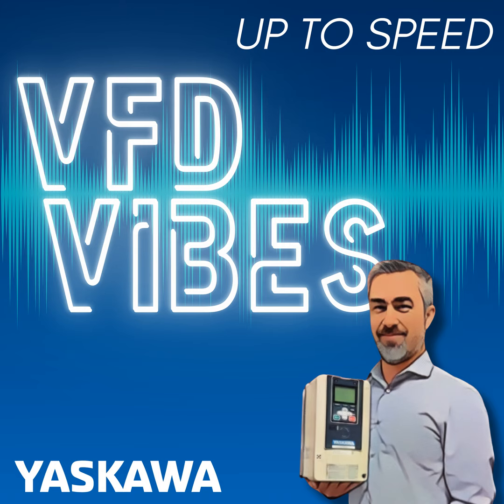And then we tripped out on this overvoltage fault, and now it's sitting there idle, and they come in the morning and reset power, and it ramps up and it's fine. Now you could look at your fault trace, your U3 group, you'll see all your overvoltage faults the last 10 times. And let's say it's happening at 5 o'clock every day. Well, maybe the signal generator or speed control, however it's configured, is running at 60 hertz. And the process shuts down, we go to a minimum of, let's say, 20 hertz, what would probably be the proper thing to adjust? Well, if we're getting it on a decel time, you'd probably want to extend your deceleration rate. The factory setting is 30 seconds. And as I mentioned earlier, I always recommended extending those accel and decel times.